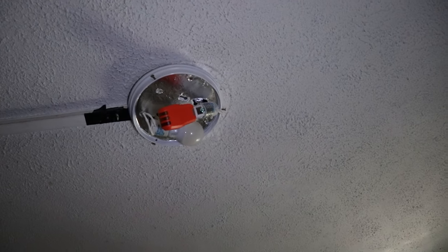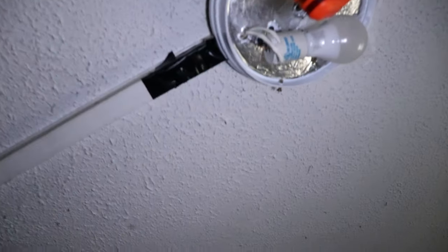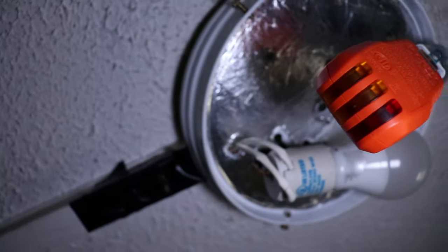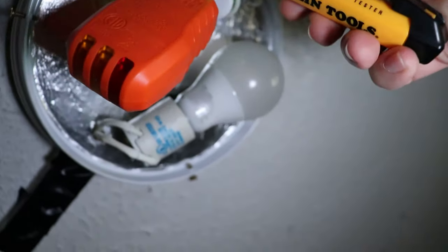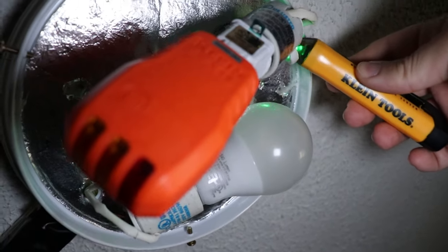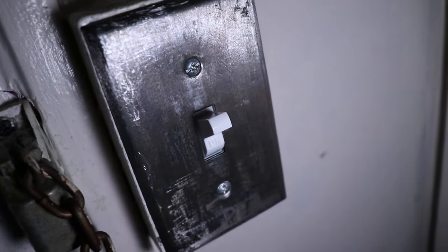Good. So as you can tell by the center light no longer being on, we have 100% knocked out the power for this circuit. However, just because of that does not mean everything is safe. So you want to go in with a voltage tester and make sure everything is 100% dead. Fantastic. Now, if we follow the conduit of the fixture down the wall, past the smoke detector, by the door, we get to our switch.